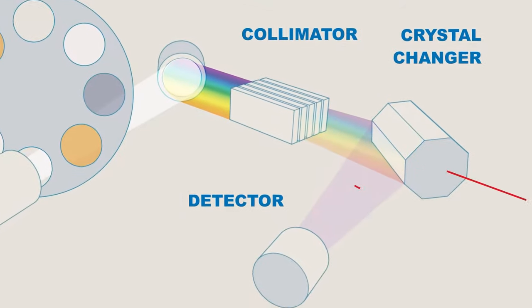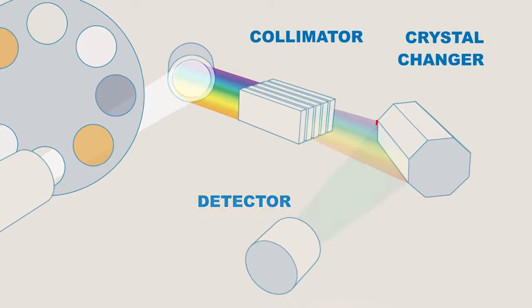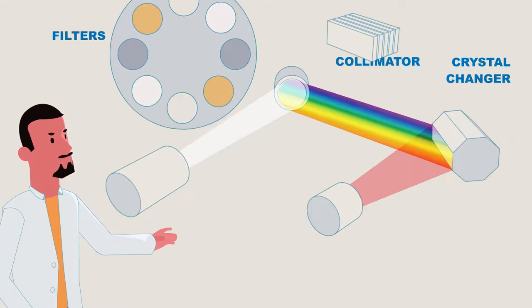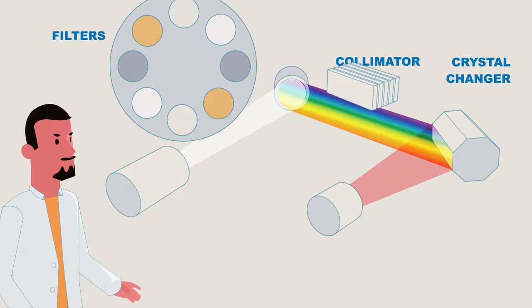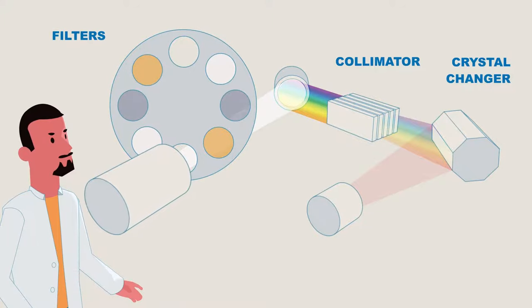The detector is positioned at 2 theta to measure the specific elemental wavelength. Placing all of these components between the signal coming off the sample and the detector comes at a cost. The intensity reaching the detector is diminished significantly. Therefore, WDXRF X-ray sources must be much more powerful.